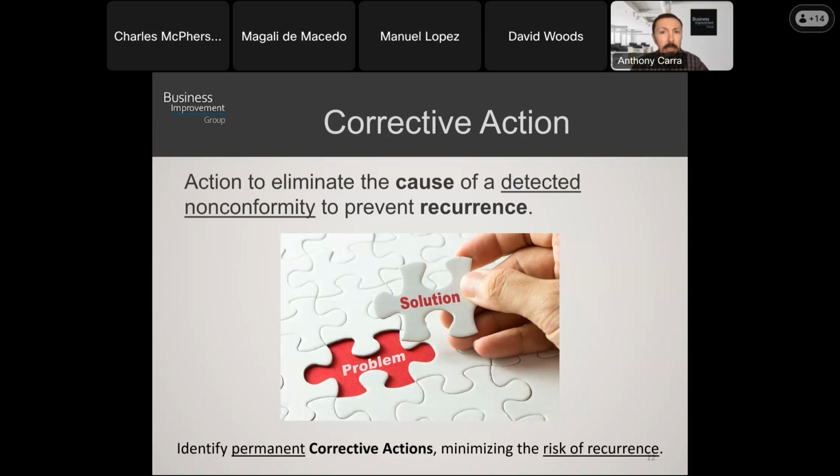Ideally, we want to at least, at a minimum, have a corrective action so that the problem that initiated the CAPA in the first place is getting addressed. But then when you are doing your investigation and you take a holistic view in your root cause investigation, once you've investigated root cause for how your problem happened, you do want to take a step back, take a systemic view and say, okay, it happened here. Knowing what I know now about this cause, could this issue have occurred somewhere else and I just didn't know about it? Or maybe there's a risk of it happening somewhere else, but just didn't materialize yet. Those are times when you can start looking at preventive actions.